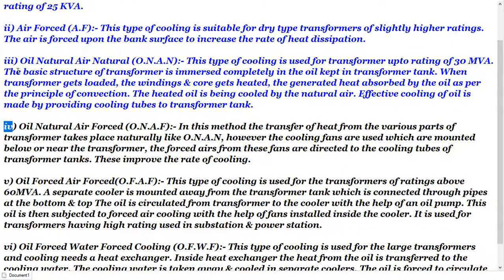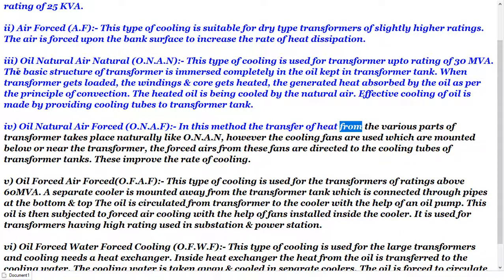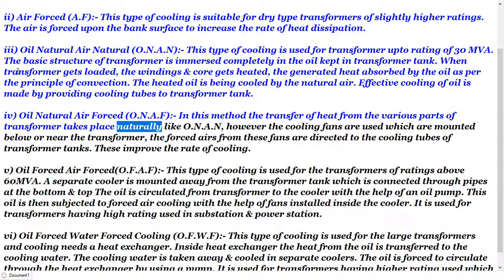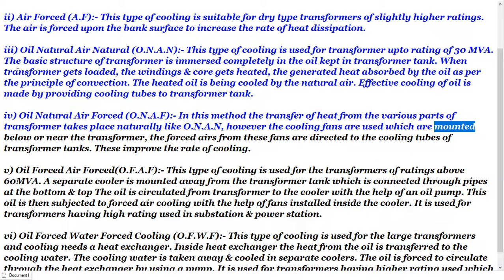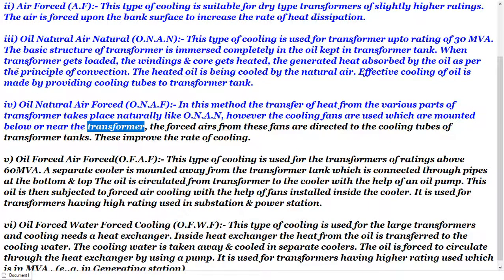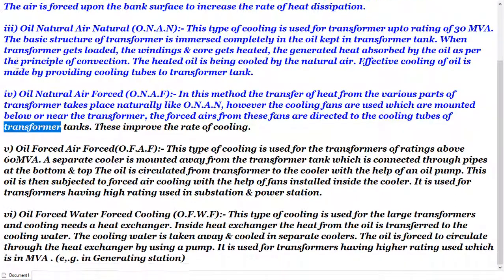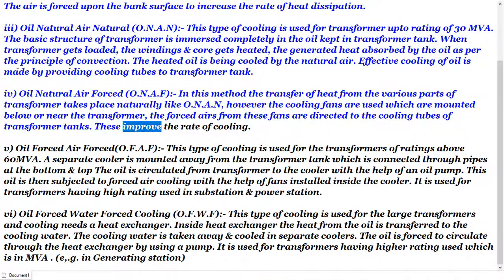4. Oil Natural Air Forced (ONAF): In this method, the transfer of heat from the various parts of the transformer takes place naturally, similar to ONAN. However, cooling fans are used which are mounted below or near the transformer. The forced air from these fans is directed to the cooling tubes of the transformer tank, improving the rate of cooling.